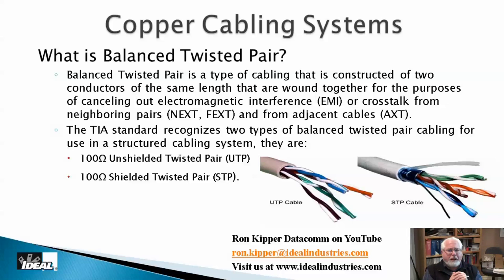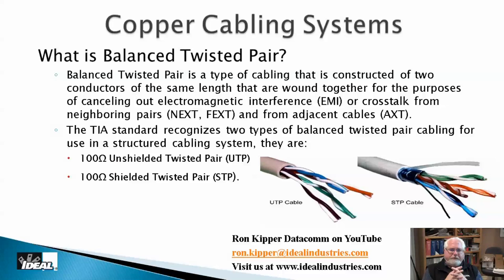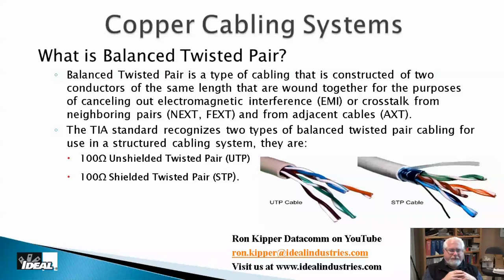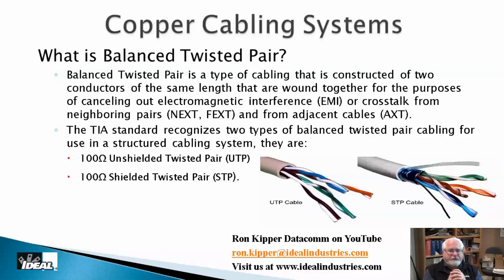This balanced twisted pair construction is very resistant to outside noise or interference. Coaxial cable, by contrast, is unbalanced and susceptible to outside noise. Category wire is rated at 100 ohms, meaning connectors, routers, and switches in the signal path are also 100 ohm. The specification is 100 ohms plus or minus 15 percent. Any difference in impedance is like a bump in the road — most of the signal passes, but some reflects back, which is called return loss.